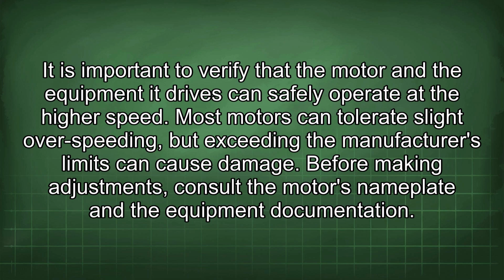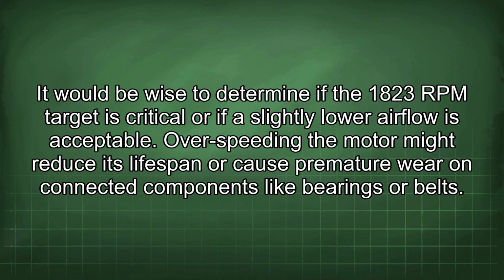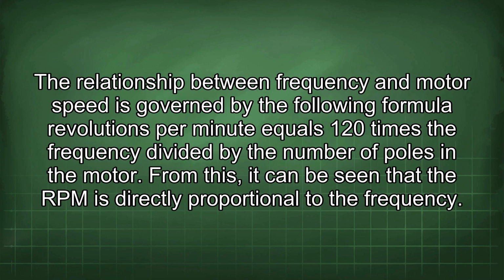Before making adjustments, consult the motor's nameplate and the equipment documentation. It would be wise to determine if the 1823 RPM target is critical or if a slightly lower airflow is acceptable. Overspeeding the motor might reduce its lifespan or cause premature wear on connected components like bearings or belts. The relationship between frequency and motor speed is governed by the following formula: revolutions per minute equals 120 times the frequency divided by the number of poles in the motor. From this, it can be seen that the RPM is directly proportional to the frequency.